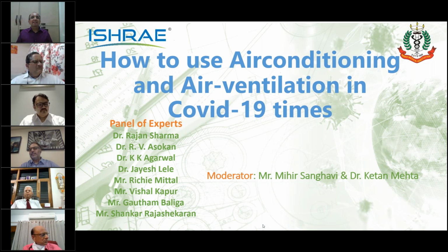The main thing is that you need to maintain your moisture levels inside the room. Come what may, COVID or non-COVID, you need to maintain pressurization inside the room. You need to ensure what is coming in is filtered. And if you're throwing out a viral load from a room as exhaust air, it needs to be treated, as Dr. Agrawal very rightly said, you need to treat viral exhaust when throwing the air out. These are some criteria you cannot do without.